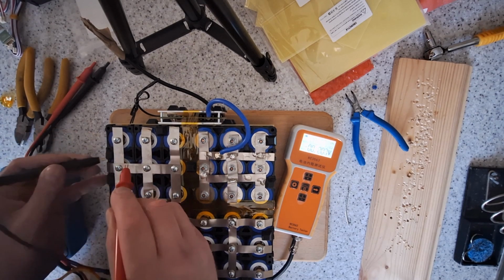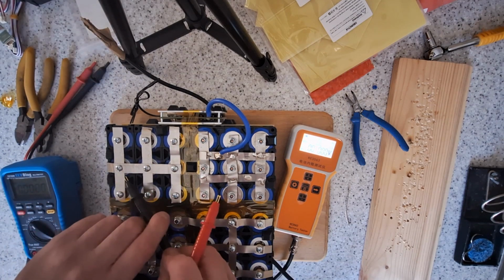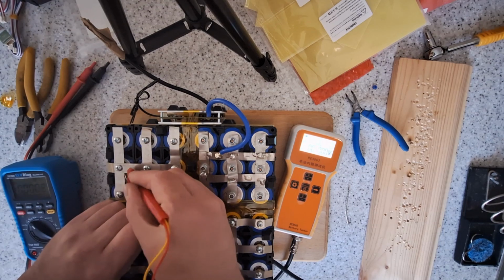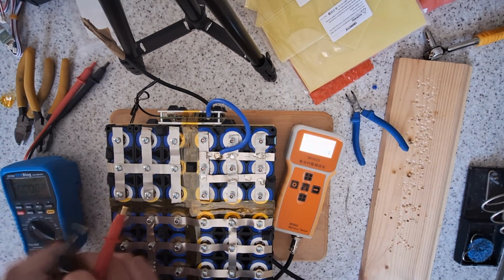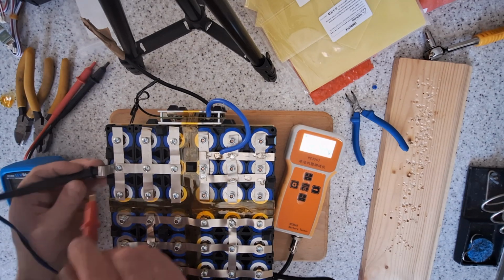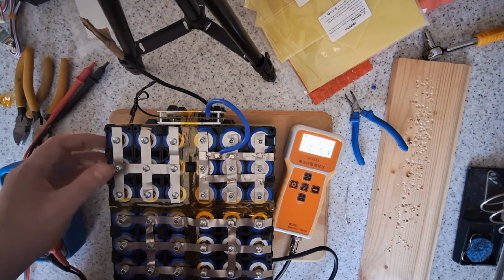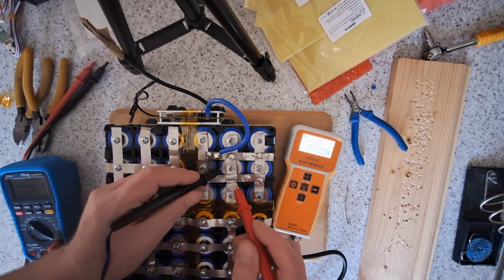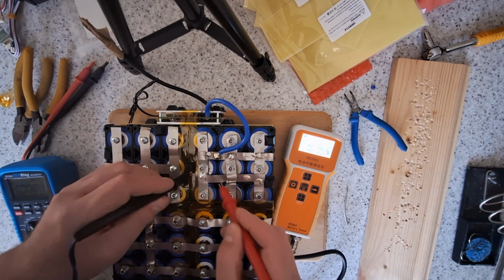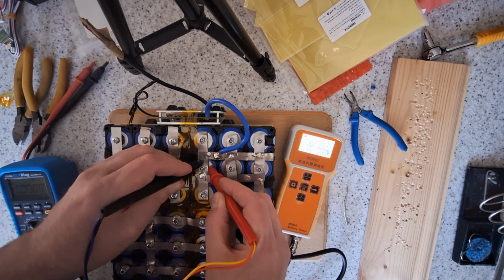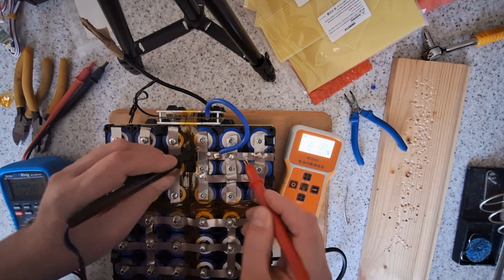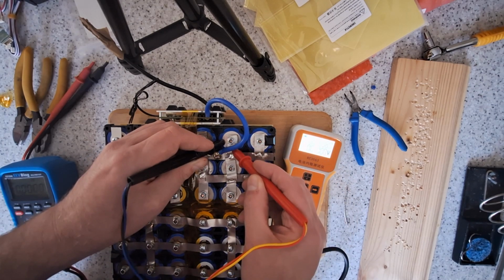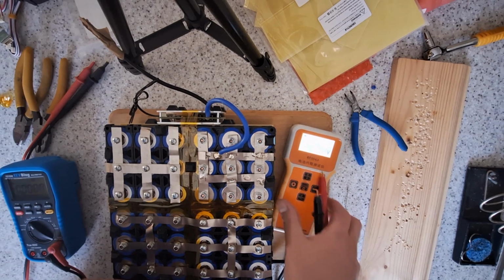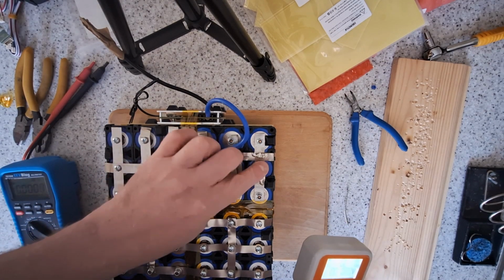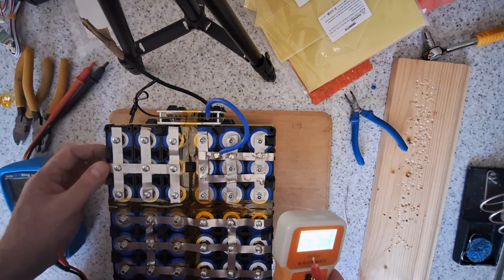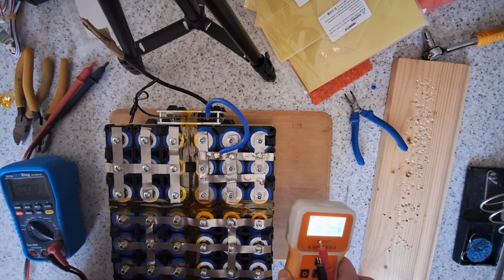0.66 milliohms on that one. I can't get that one on there, but 0.66 again. Then I'll repeat that for every single connection: 0.62, 0.55, 0.58, 0.65. I'll repeat that for every single cell. That will reveal if there's any bad connections between the cells, which will cause high resistance and cause it to get hot. I'll just do that now and then come back.